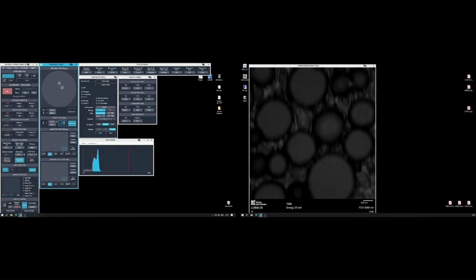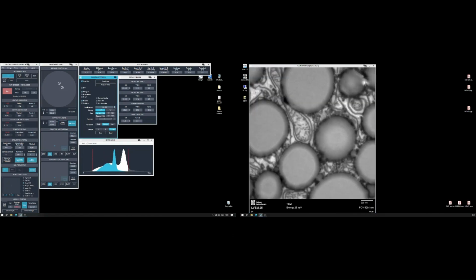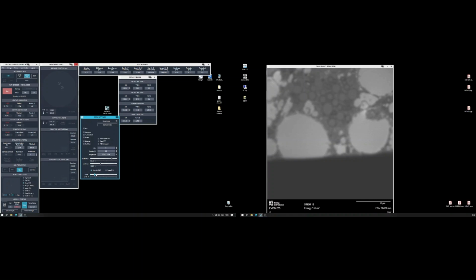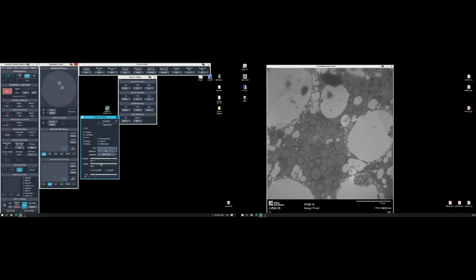Okay, we will increase the magnification a little bit to focus on this nice mitochondria, and we can also try scanning transmission mode on this specific place. We have to turn on the photomultiplier because in the beginning it's turned off for security reasons. Now we have to focus. The image is almost focused, at least as far as I can recognize at this magnification, and I have to play a little bit with the contrast and brightness.